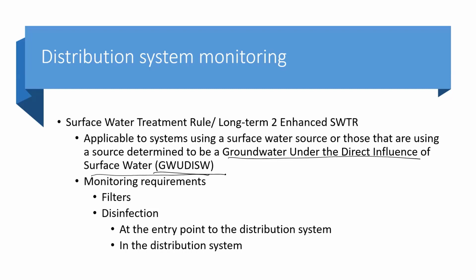Okay. And that supernatant, because it was pumped back to the head of the plant and because it was outside, it becomes a groundwater under the influence of surface water. And then the surface water regulations impact that plant. So they were looking at some very significant modifications to change their process so that that backwash water did not go out into those ponds.